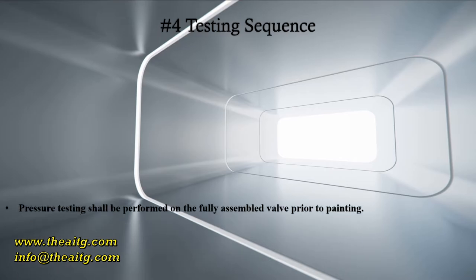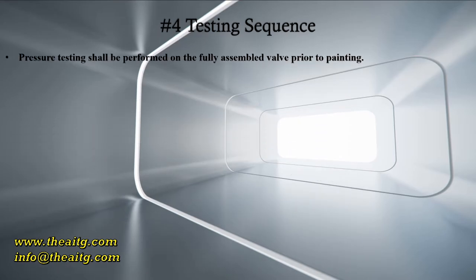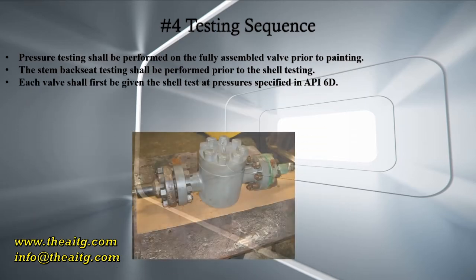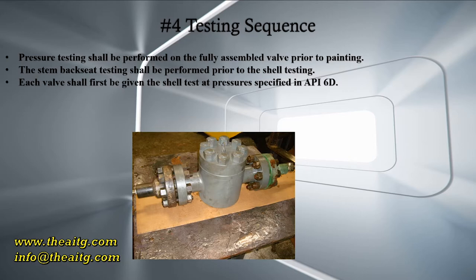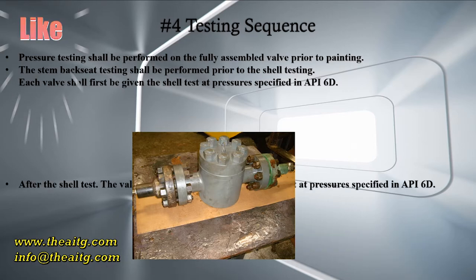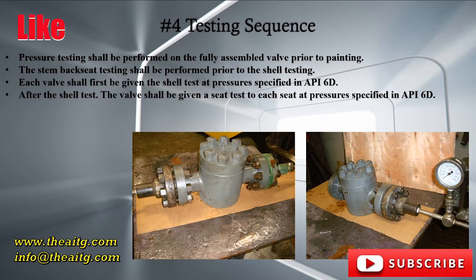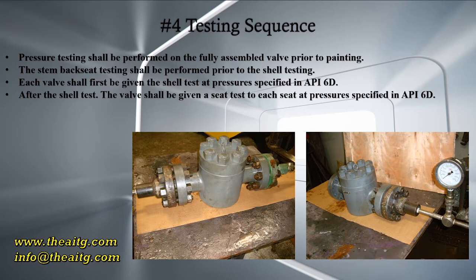Testing sequence: pressure testing shall be performed on the fully assembled valve prior to painting. The stem backseat testing shall be performed prior to the shell test. Each valve shall first be given the shell test at the pressure specified in API 6D. After the shell test, the valve shall be given a seat test to each seat at the pressure specified in API 6D.